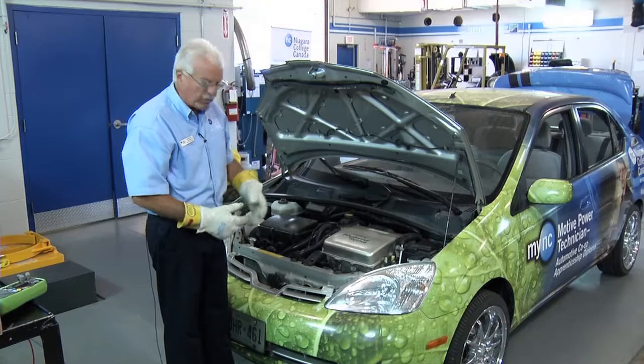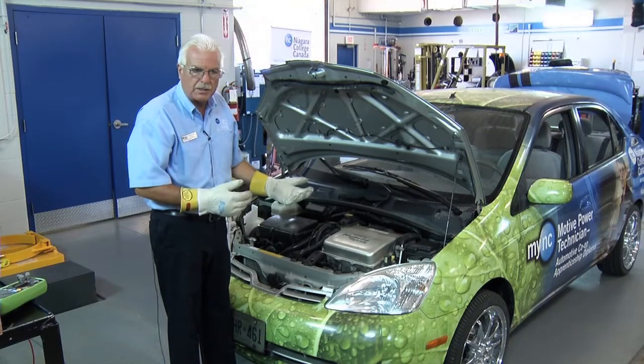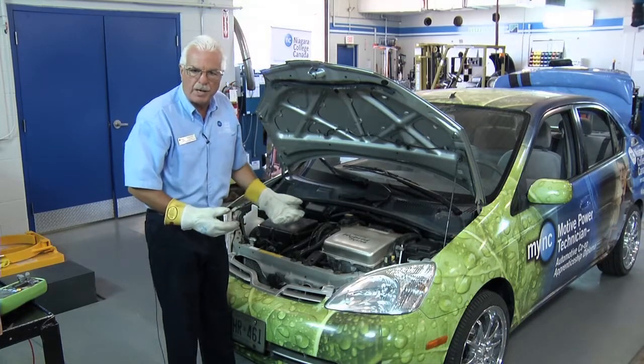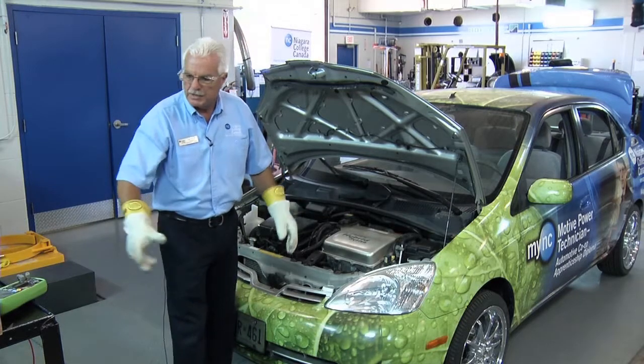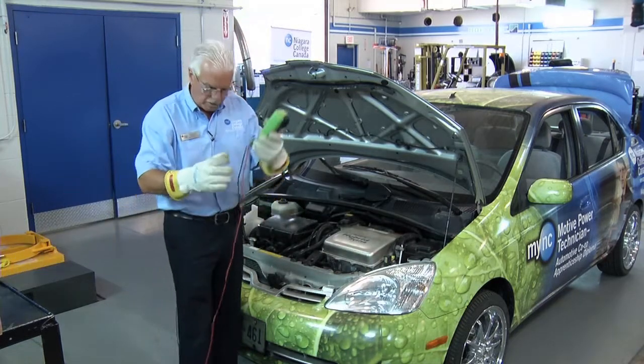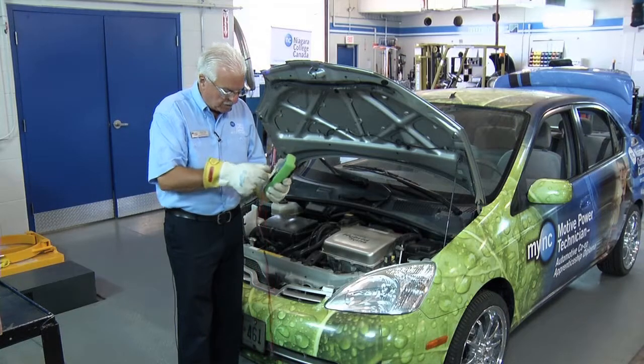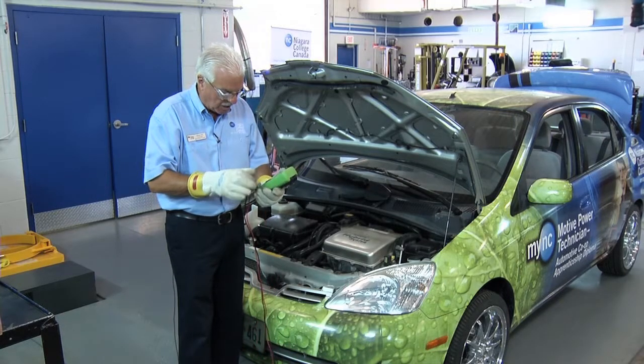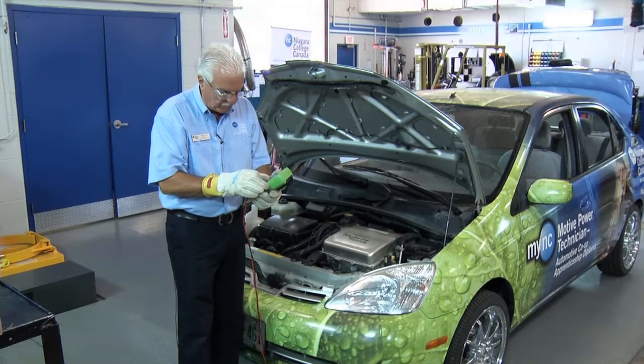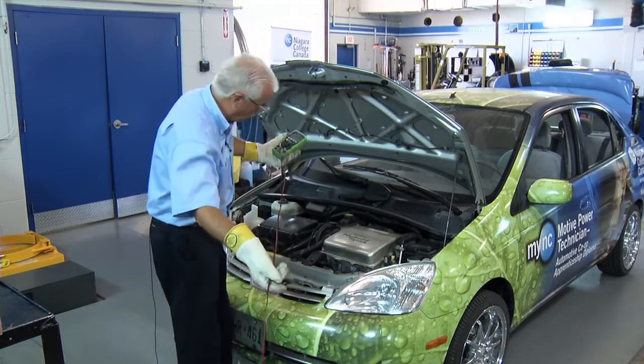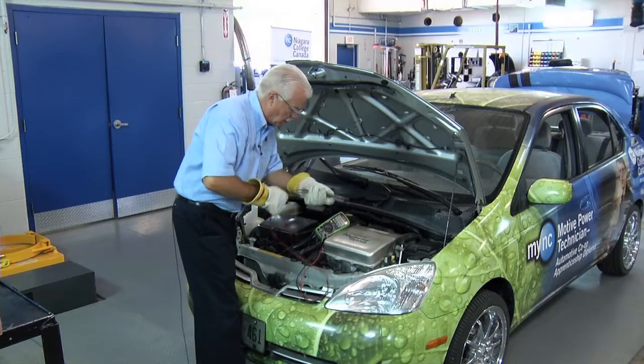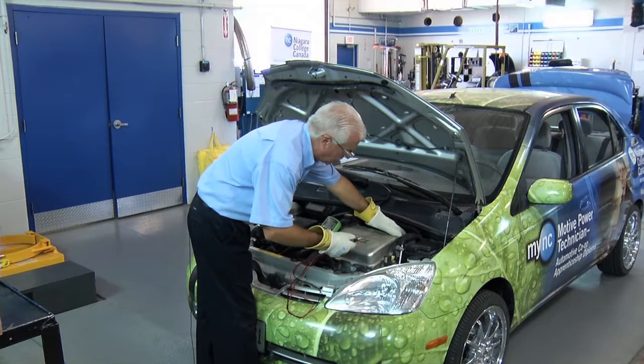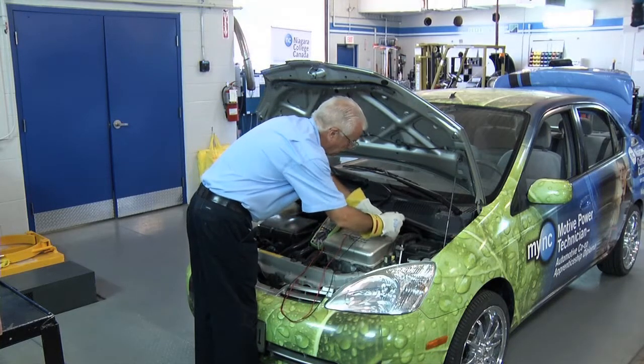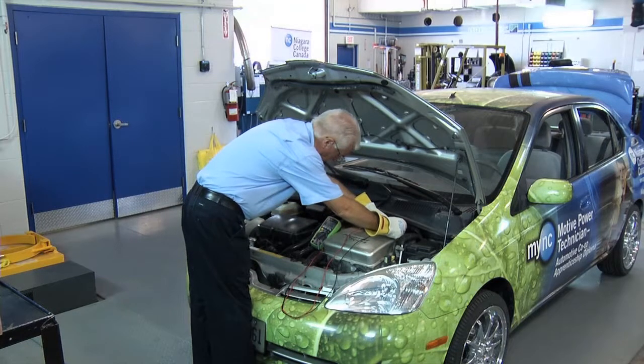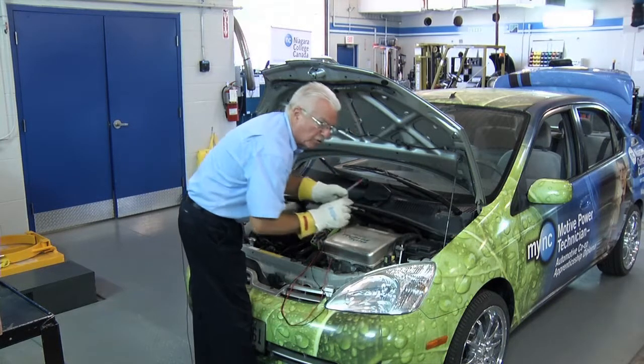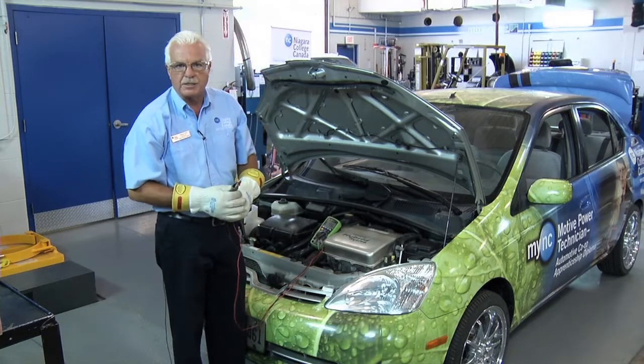Now that our 10 minutes have basically expired, the capacitors should have drained. Next we take our high voltage voltmeter, set it to the voltage scale, and we're going to be looking at roughly 300 volts. We go in with the voltmeter, disconnect the orange connector, and then identify that there's 0 volts showing on the meter.